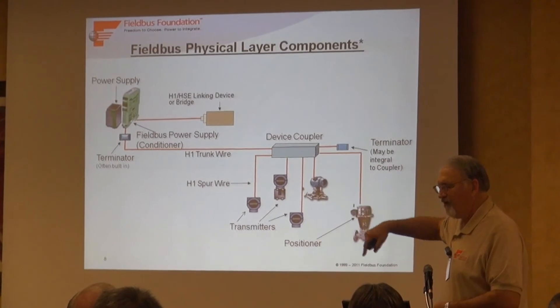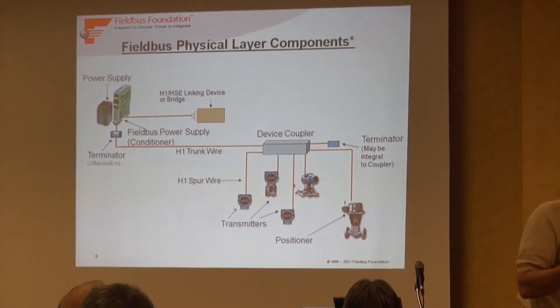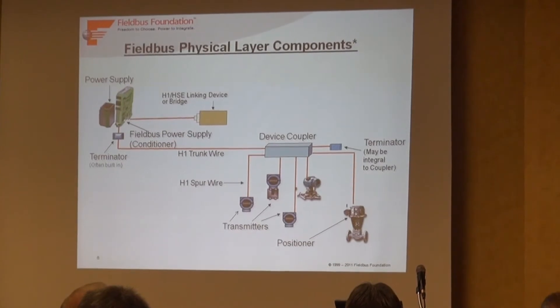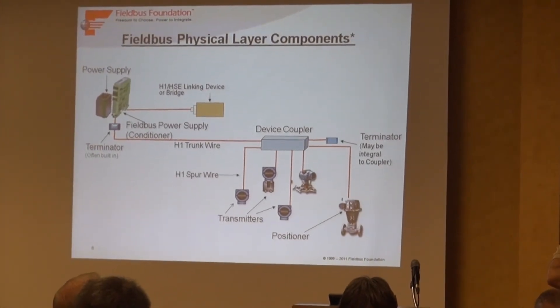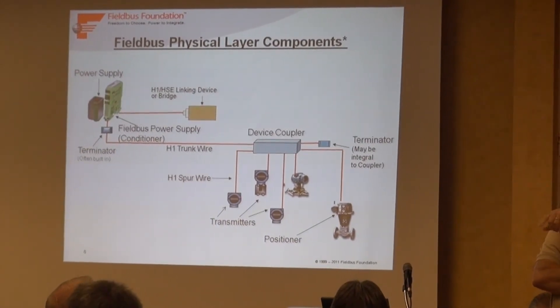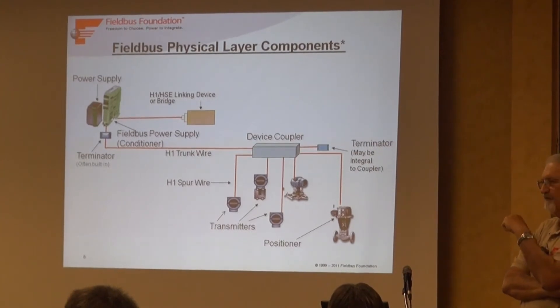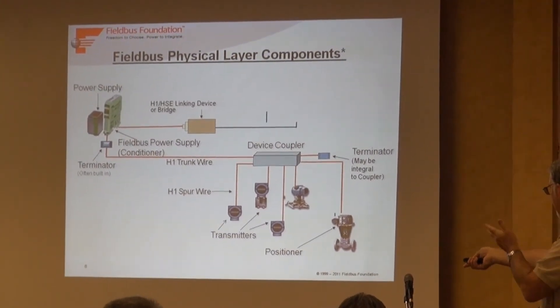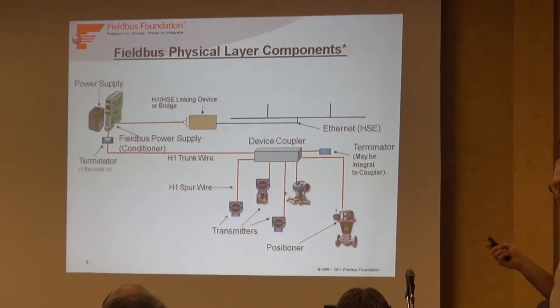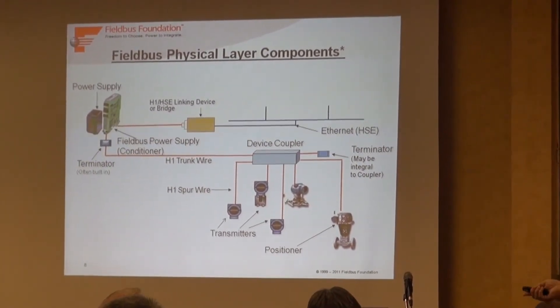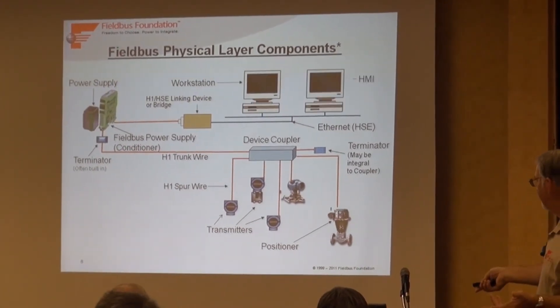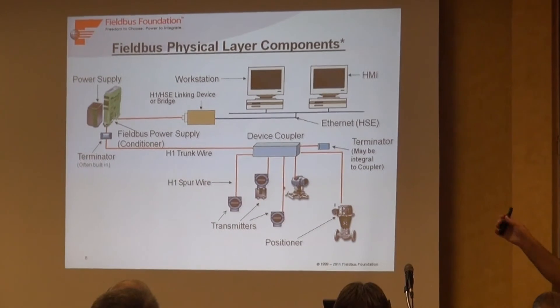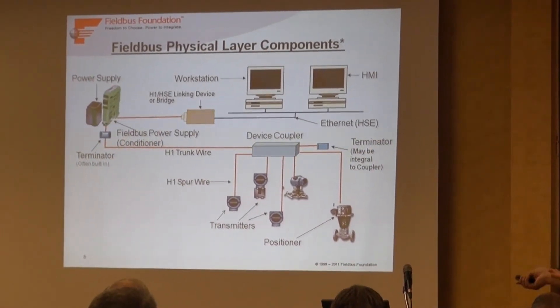To be able to talk to a host system or actually see something on the screen, you're going to have to have some sort of bridge, linking device, or H1 interface. That's usually where the LAS - the Link Active Scheduler, this traffic cop - resides. That's the one that sets up the schedule and keeps track of who's on that segment, which one's talking at the proper time, and that sort of thing. Add this linking device and now you may have high-speed Ethernet or HSE interfaces going to your workstations and HMIs. It's basically as simple as that: one pair of wires, many instruments. We'll talk about how many is many.